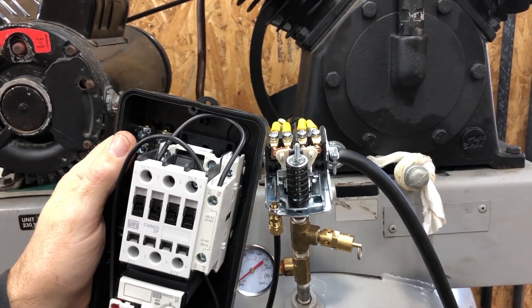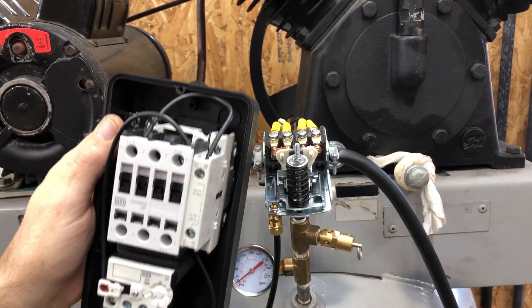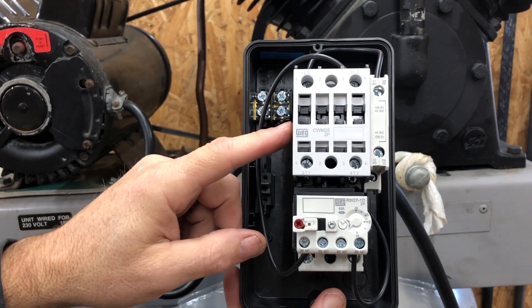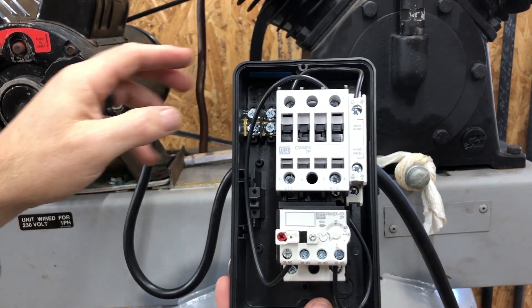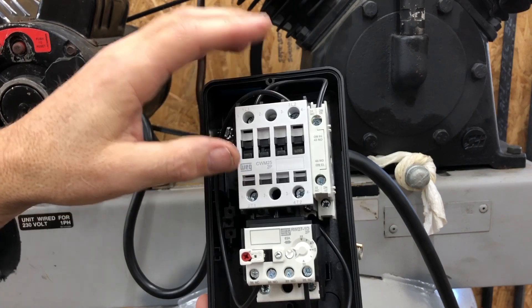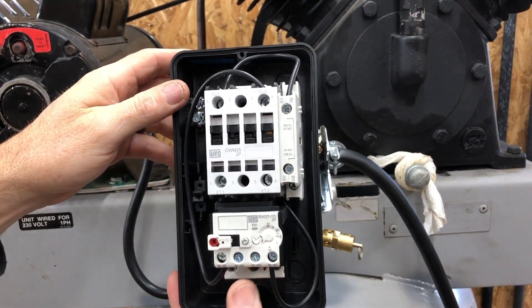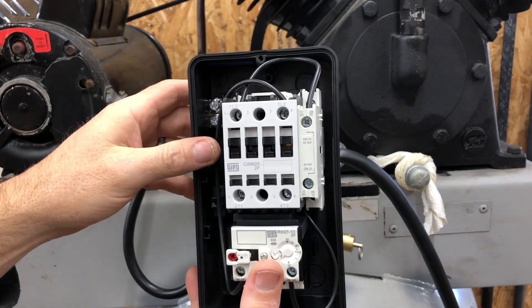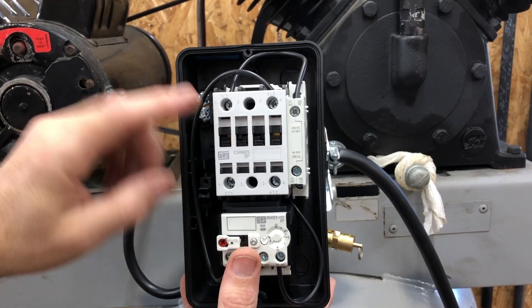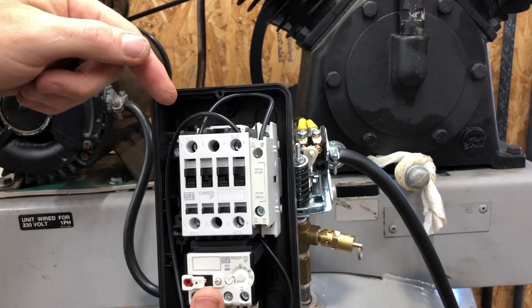I'm going to replace the pressure switch — got a new pressure switch that's actually low-rated like the original — but this magnetic starter is going to take care of the startup of the motor. This is basically a big magnetic relay, and the relay will handle all the high voltage so the pressure switch won't be handling the high voltage anymore. I'll get into detail on this particular one, which is made by WEG. Basically we're going to have our two hot wires coming in to L1 and L2.